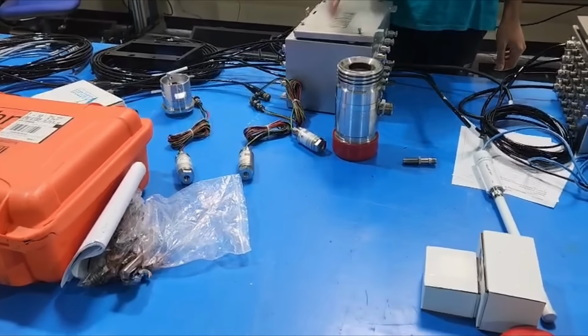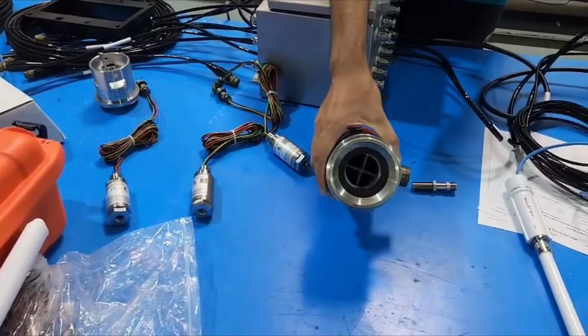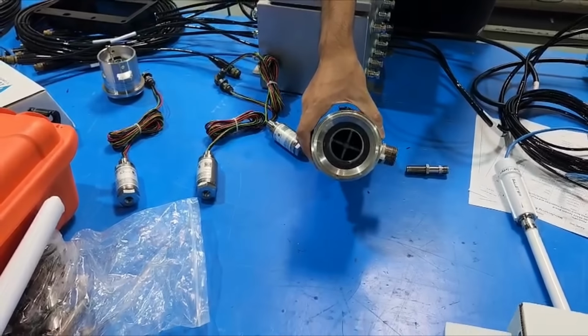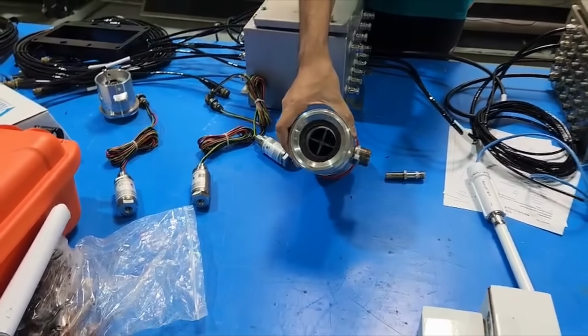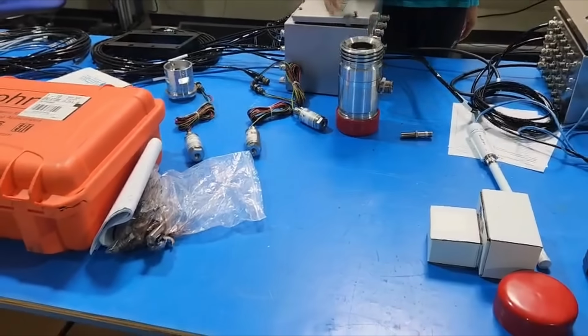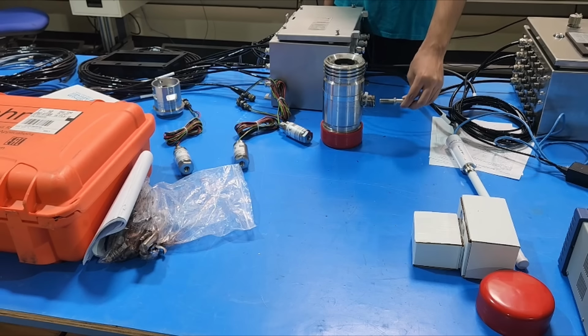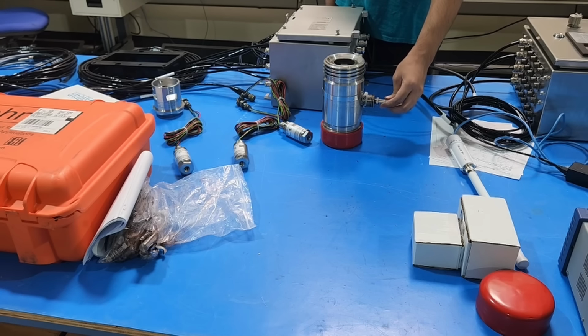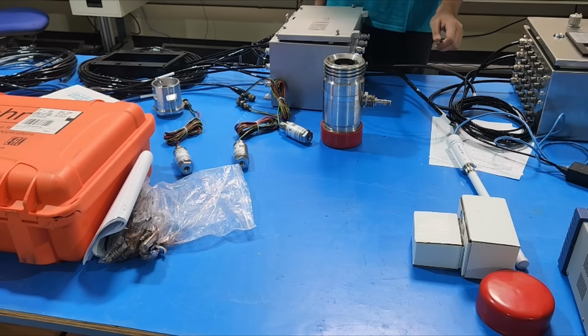Inside of it is a small high-speed turbine that rotates with the fluid flow. The speed of the turbine is proportional to the flow rate of the fluid being measured. The movement of the turbine is measured by a magnetic pickup that senses the rotation of the turbine. This type of flow meter can only be used with non-abrasive fluids such as water, oil, brine, etc. Mud or slurries can cause the turbine blades to wear very quickly.